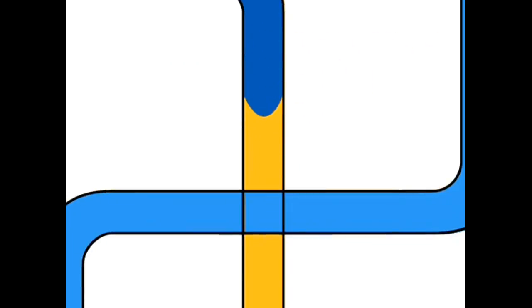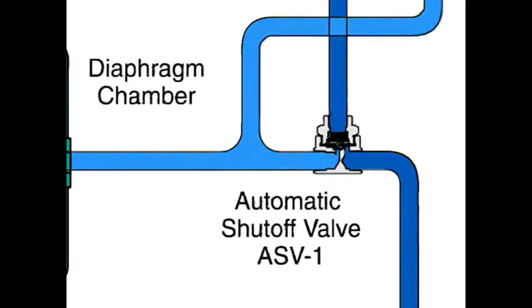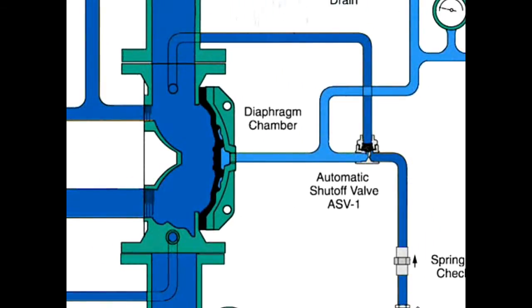Water also passes through the trim to the automatic shutoff valve to close this valve. Once closed, it will prevent the diaphragm chamber from becoming inadvertently re-pressurized.